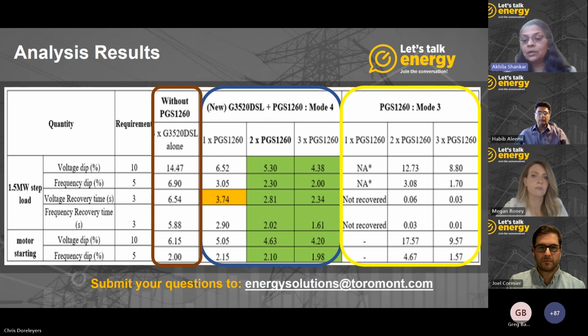In the yellow box, we subjected only the battery energy storage systems to the same set of loads, and the results were recorded. As you can see here, subjecting 1 unit of battery energy storage system does not make sense because the base load is 1.5 megawatt. The first step load is 1.5 megawatt, and we are talking about a single 1260 kilowatt rating of battery energy storage system. So we look at the 2 units when they were subjected to the same set of loads.